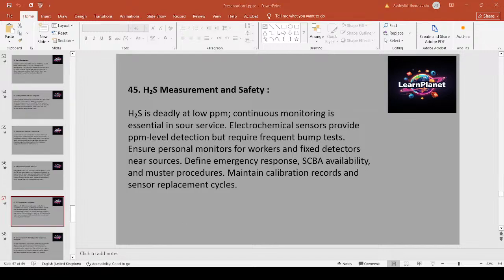H2S is toxic at low ppm and can be lethal. Continuous monitoring with fixed and portable detectors is essential in sour service. Use electrochemical or TDL sensors depending on required sensitivity and environment. Bump test daily and replace consumables per manufacturer recommendations. Define evacuation, SCBA availability, medical response, and muster procedures for detected levels. Keep training, PPE, and sensor calibration logs current. Example: in a sour gas well site, require personal H2S monitors for all personnel and fixed detectors near wellheads with audible and visible alarms and automatic shutdown logic for high readings.